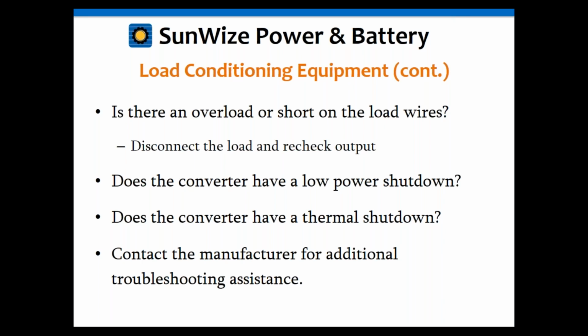Some of them have a low power shutdown. I've actually had this problem a lot with inverters recently. You might have a load that's as little as, I don't know, 5 or 10 watts, and on some of these inverters they have what they call an idle mode, a low power shutdown, such that if your load is less than a certain value, it could be as little as 10 or 15 watts, then it thinks there's no load and goes into idle mode so that it reduces its parasitic load on the system. So if you have a small load, you might have that as a problem. You might need to disable that feature.